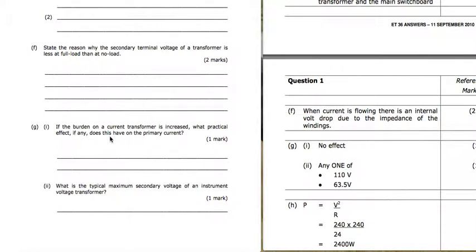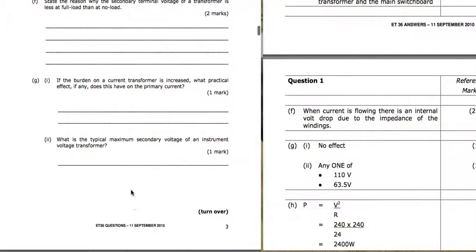If the burden of a current transformer is increased, what practical effect does it have on the primary current? It's not going to change the actual primary current, so no effect. Typical secondary voltage of an instrument voltage transformer. So they give you two, 110 and 63.5. I generally just remember 110, so you get 110 volt instrument voltage transformers.